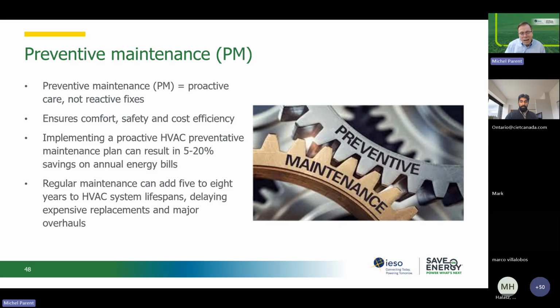resources are, what they can achieve, and then prioritize. Everything that has a high impact on tenant comfort and on reliability of the equipment should be at the top. And then energy efficiency should not necessarily be what creates the top preventive maintenance action. It should be reliability, it should be tenant comfort, and efficiency will come along with that. Usually, if you have a proper PM program compared to no PM program, or a reactive PM program, your savings will be in the 5 to 20% range. And if you had purely reactive and very little, even informal, PM, you're likely going to be close to that 20% rather than the 5%.